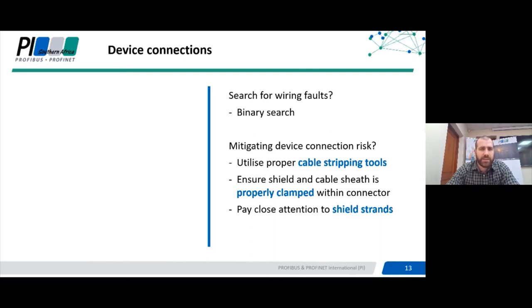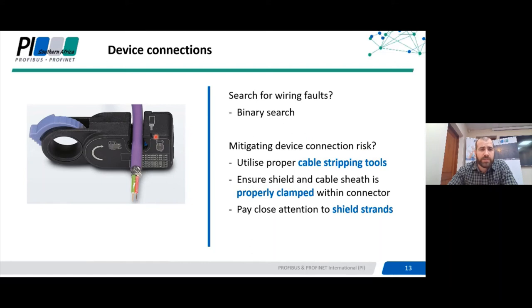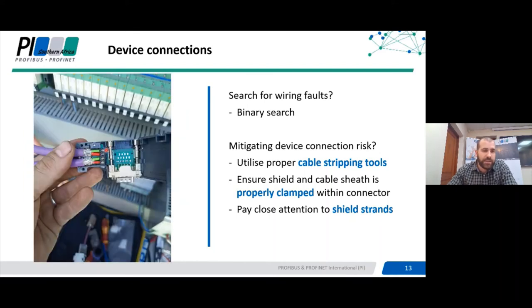To mitigate device connection risk, firstly utilize a proper cable stripping tool. This tool has two blades set at different depths: the first blade removes the outer sheathing, and the second blade scores and cuts off the shield but leaves a good one centimeter of shield to make good contact with the ground bar. Pay very close attention to the shield strands — sometimes not all strands are cut and one can accidentally go up towards the A and B lines, causing a short that can destroy an entire network on Profibus. As you create new plugs, make sure you test the cable and segments to ensure they are in a good state.